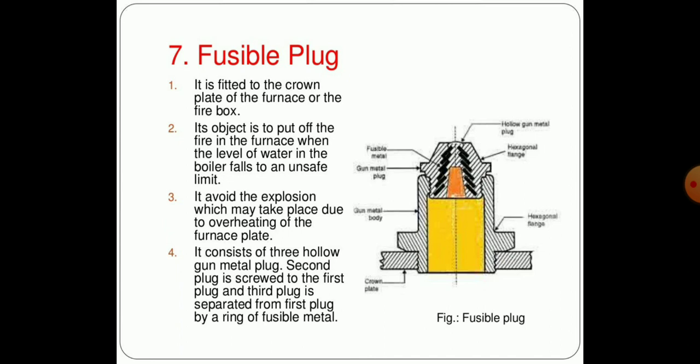Another important mounting of the boiler is the fusible plug. It is fitted to the crown plate of the furnace of the firebox, and its main object is to put off the fire in the furnace when the level of water in the boiler falls below the unsafe limit. It avoids the explosion which may take place due to overheating of the furnace plate. It consists of three hollow gun metal plugs: second plug screwed to the first plug, and third plug which is separated from the first plug by a ring of fusible metal.